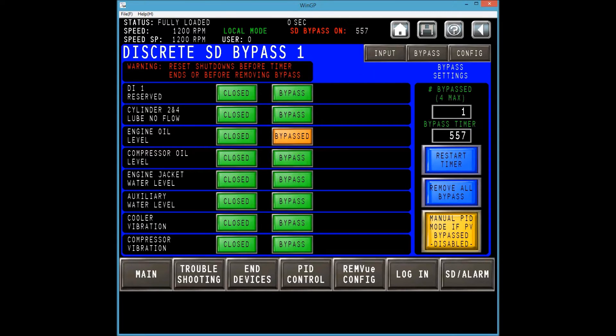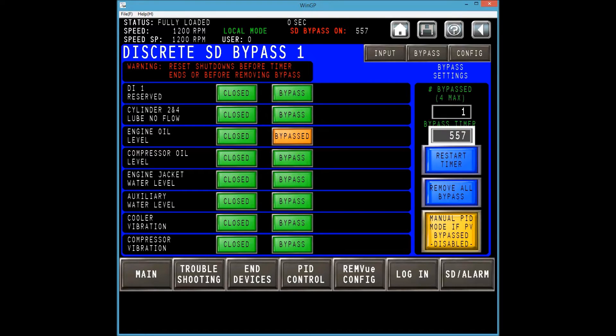If the bypass is successful, you will notice three changes on the screen. One, the green bypass button will change to orange. Two, the bypass counter on the right will increase by one. Three, the bypass timer will start counting down. The bypass counter is limited to four channels, meaning a maximum of four I.O. channels may be bypassed at one time across all I.O. channel types — DI, AI, or TC. The bypass timer is a 10-minute timer that will reset the bypass state when it expires in case the user forgets.